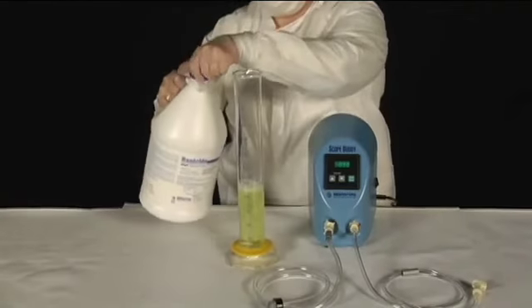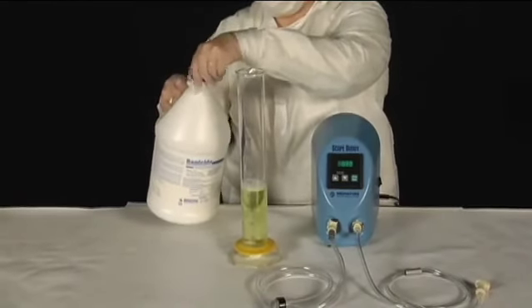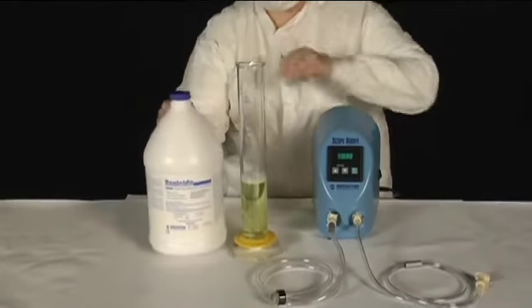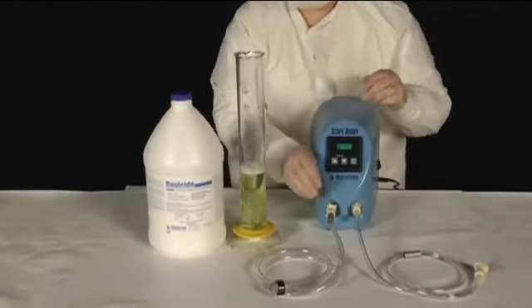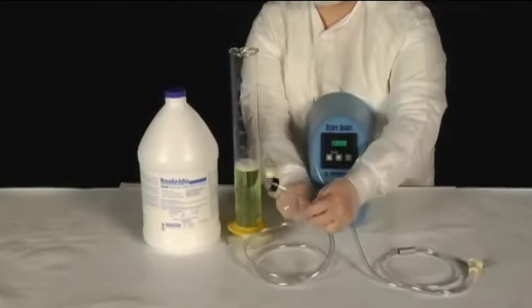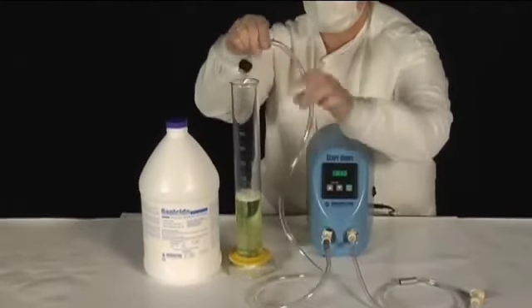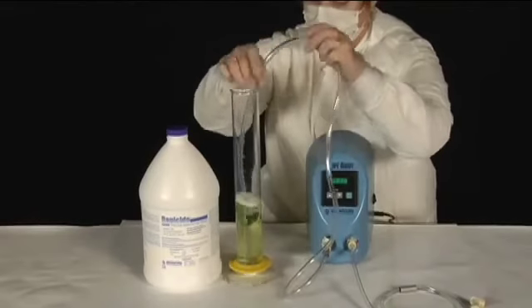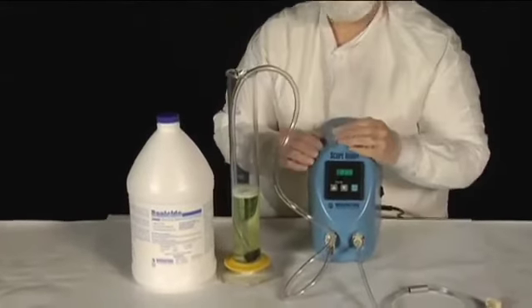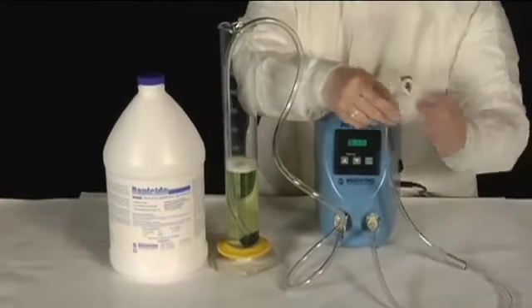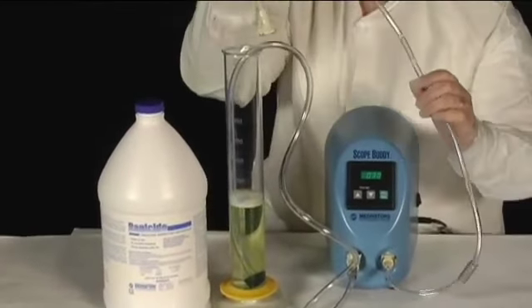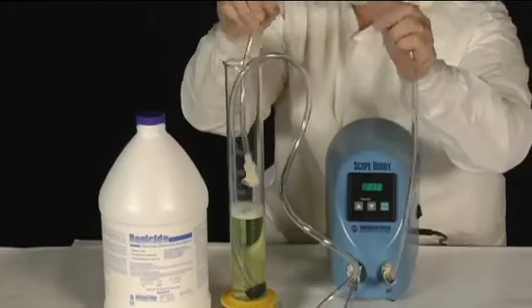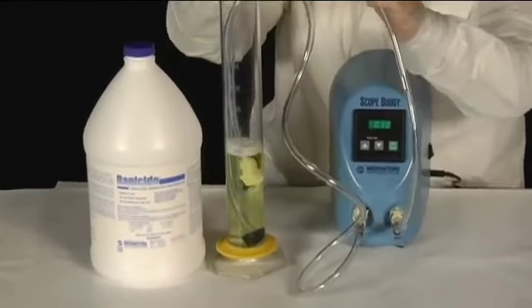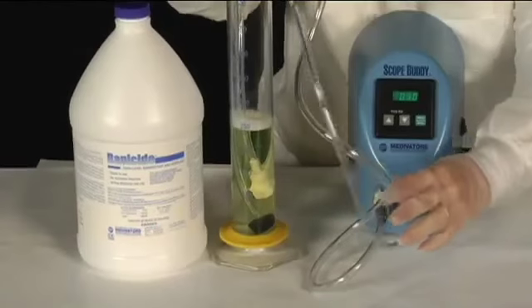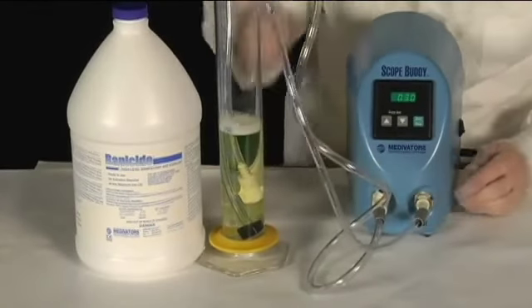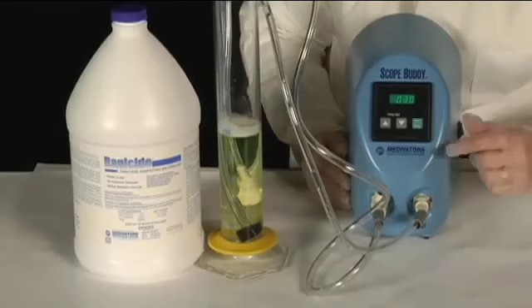The decontamination procedure is simple to set up and perform, and although it can be run at any time, it is recommended that it be carried out at the end of a workday. Therefore, the device should always be powered on and all tubing attached. Place the screened end of the fluid intake line into a basin of decontamination solution, ensuring it is deeply submerged. Also place the open end of the outflow tubing into the basin of decontamination solution. Using the front panel arrow keys, set the timer until it displays 2 minutes.